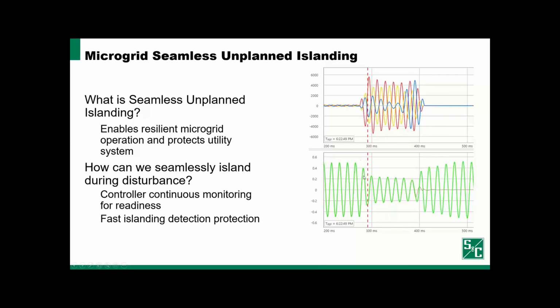You can see at fault inception, the voltage starts collapsing and retains at a collapsed level throughout the fault. And you can see just one line over on the left. But right here, there's a red line that separates from the green lines. This is showing that the system voltage winds up collapsing after we separate, while the islanded system actually recovers.